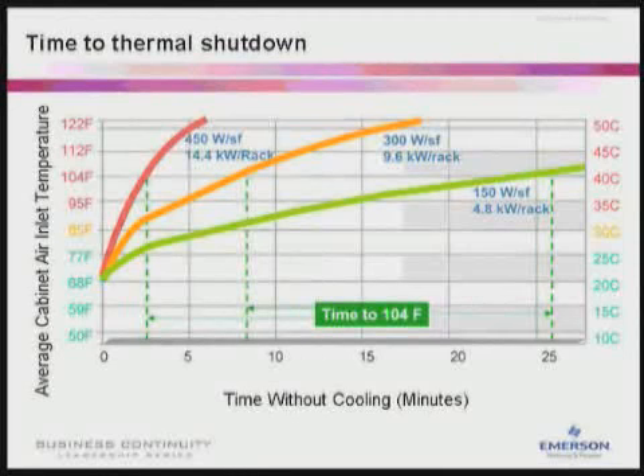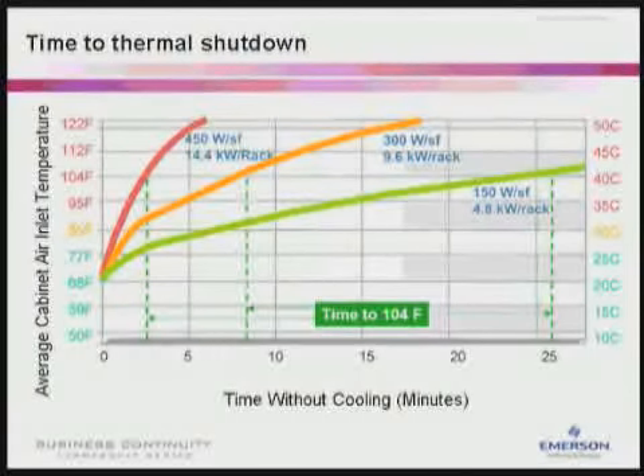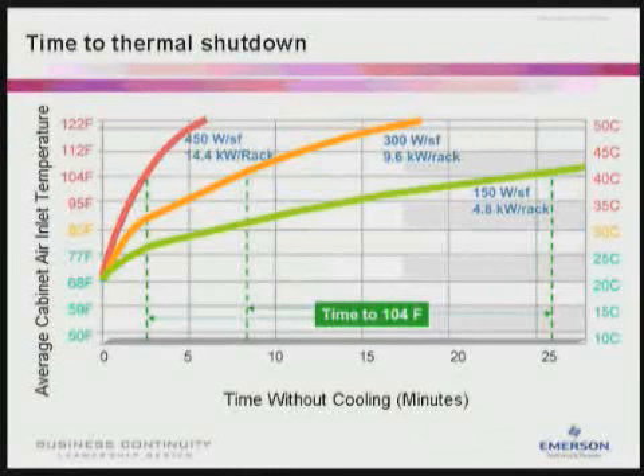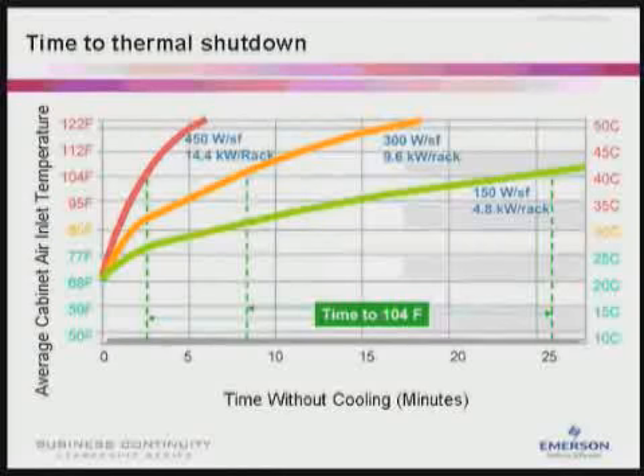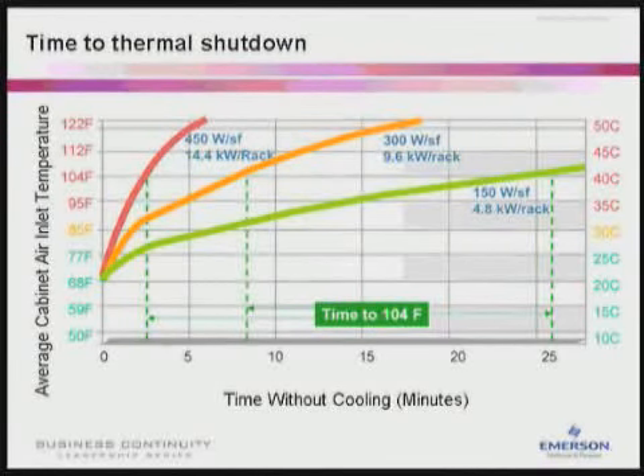If you lose cooling in a facility where your average rack is about 5 kW, you've got about 25 minutes to address the problem. If your average kilowatts per rack is about 14.5, which we're seeing in some installations today, you've got about 2 minutes. Obviously, this is an issue that needs to be addressed in your business continuity planning if you plan on staying up for more than 2 minutes after cooling loss.